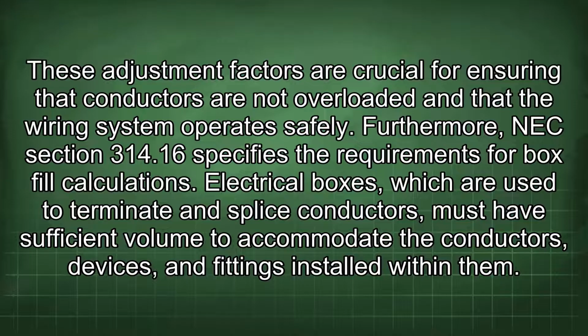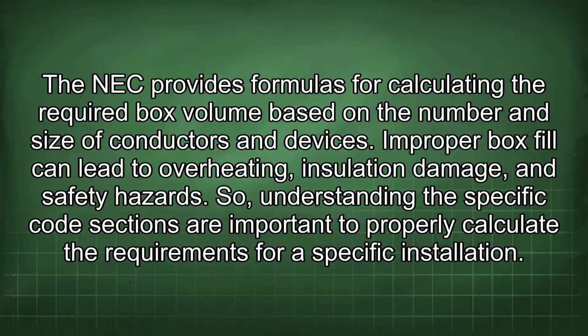Furthermore, NEC Section 314.16 specifies the requirements for box fill calculations. Electrical boxes, which are used to terminate and splice conductors, must have sufficient volume to accommodate the conductors, devices, and fittings installed within them. The NEC provides formulas for calculating the required box volume based on the number and size of conductors and devices. Improper box fill can lead to overheating, insulation damage, and safety hazards. So, understanding the specific code sections is important to properly calculate the requirements for a specific installation.